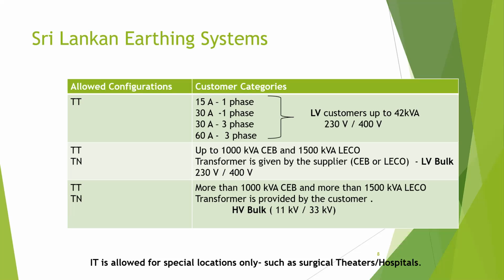So those systems are used in special locations such as surgical theaters and hospitals, where you need continuity of supply. Even if there is an earth fault in your system, you should be able to continue the operation. So in surgical theaters we have IT systems. Usually in IT systems they have a separate transformer, and after that separate transformer they will have the surgical theater. That's how IT systems are wired.